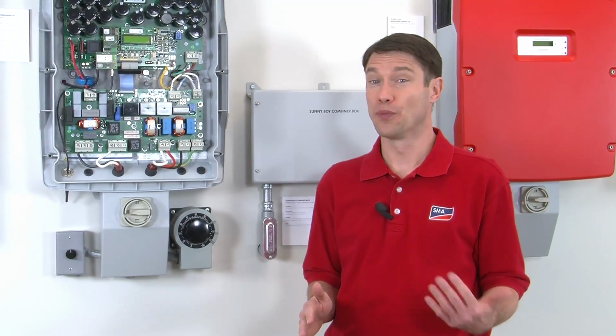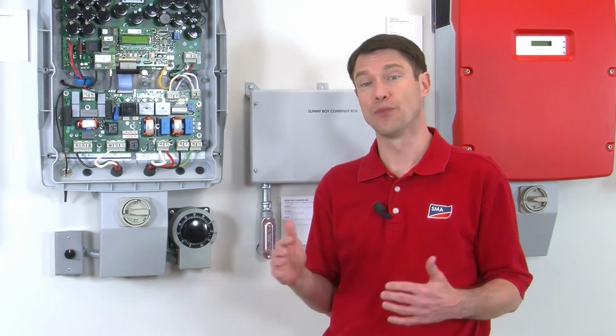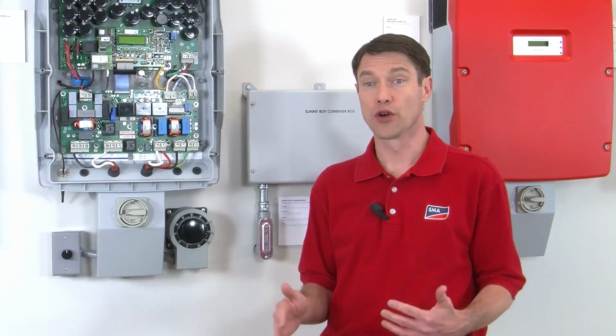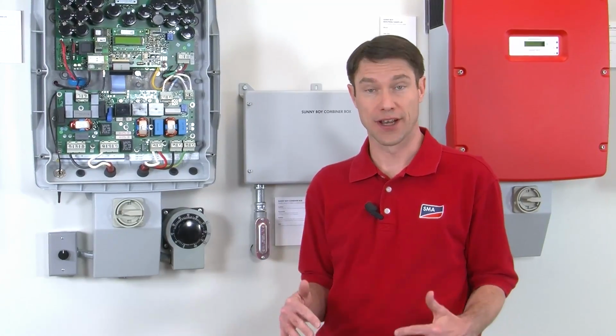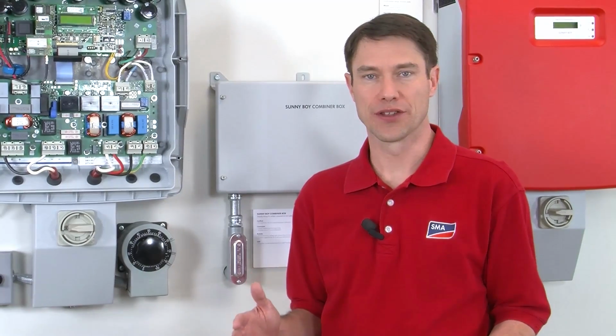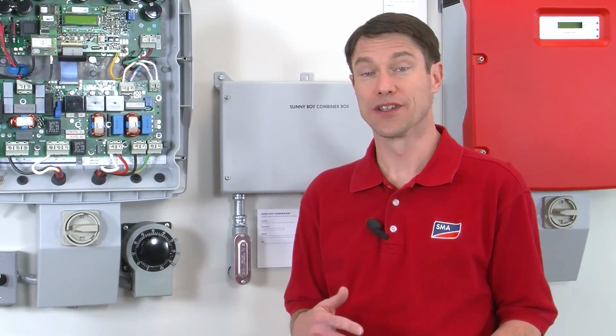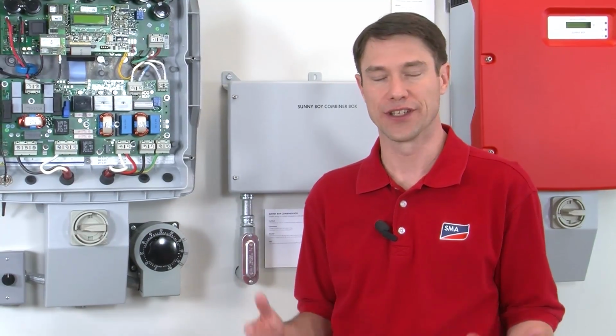But if the frequency goes below 59.3 or above 60.5, the inverter will see that as an error and disconnect from the grid. So when the frequency of the grid goes outside of those limits, the inverter will disconnect and it'll put disturbance FAC on its display. So you'll see that's the error that it's seeing.